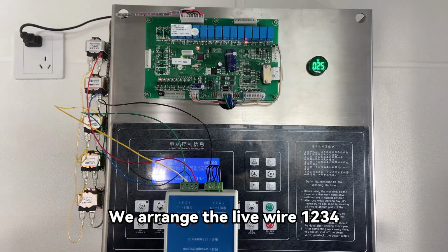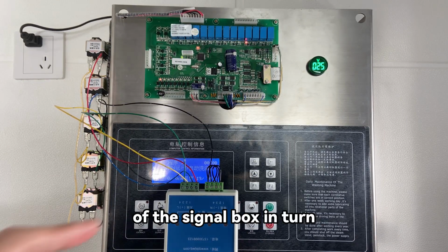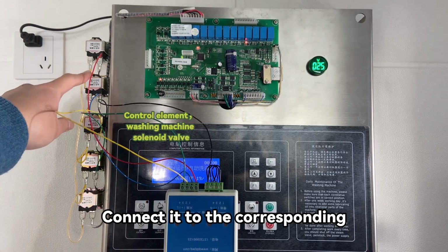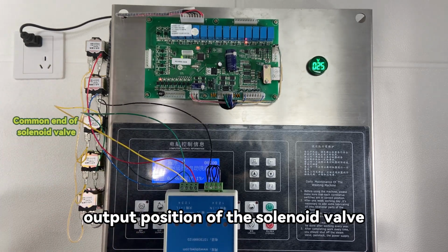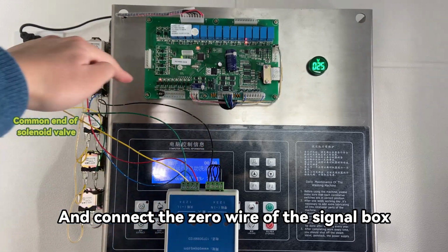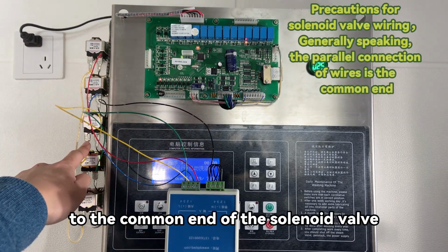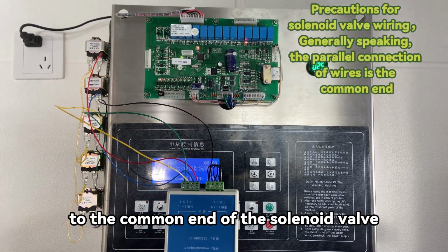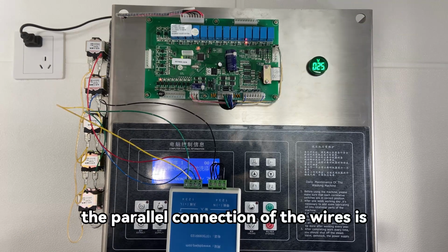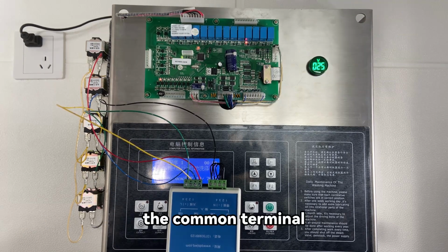We arrange the live wire 1, 2, 3, 4 of the signal box in turn and connect it to the corresponding output position of the solenoid valve, and connect the 0 wire of the signal box to the common end of the solenoid valve. Generally speaking, the parallel connection of the wires is the common terminal.